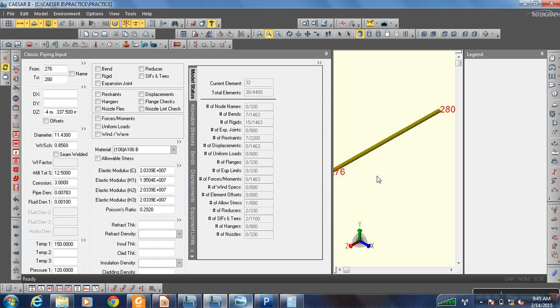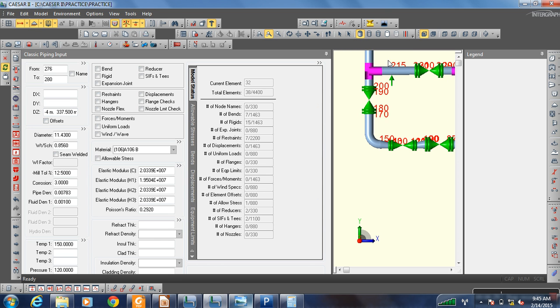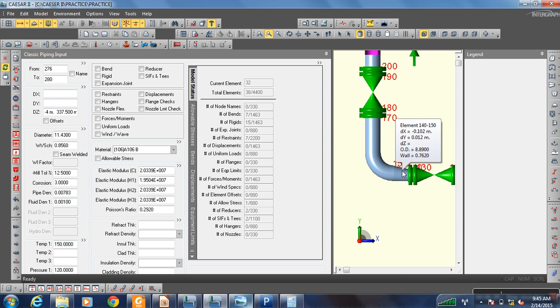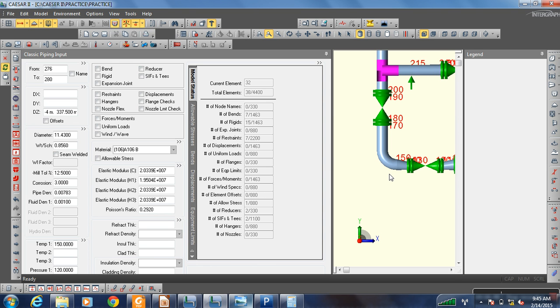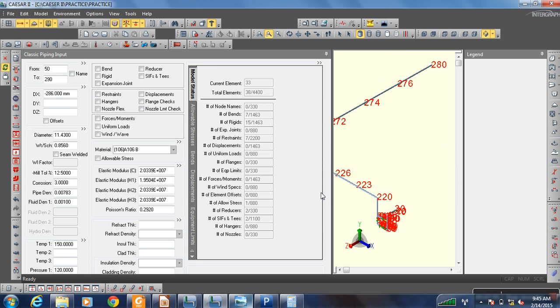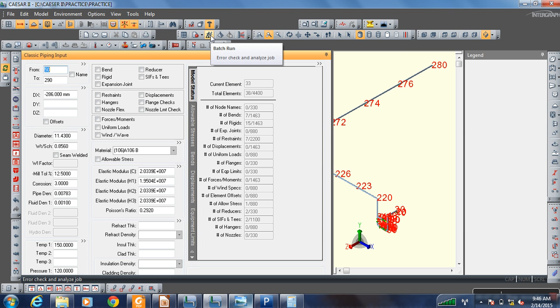Keep spacing under five meters so as not to exceed five meters. We want a support here also, so we will edit — this will move again. Now putting supports for this one is done; piping support is done. We want to check the errors in that pipe — if some error is coming it will show here. No error is there. Now for this batch run, this means it will analyze the piping with supports, whether it is under the given load or exceeding it.